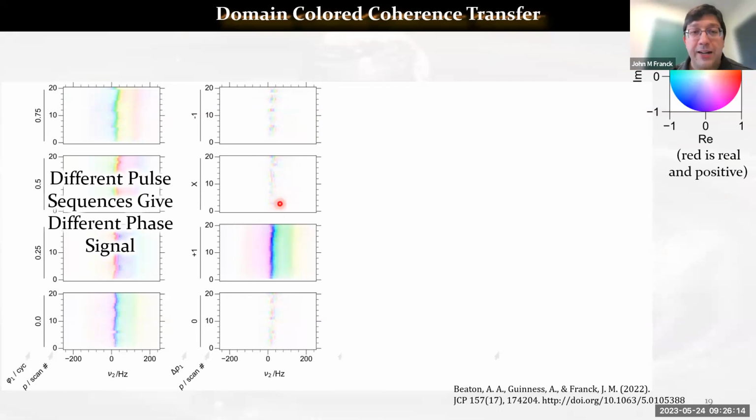But you'll notice that in our case, we have this extra smudging here that we like to call phase cycling noise, right? This comes from the imperfections in our system, and specifically you'll notice that with each individual transient our resonance frequency is bouncing around, right? Because our Bruker electromagnet, just the way it's designed, does not control field that accurately, okay?